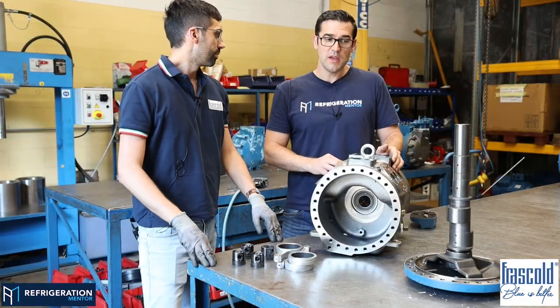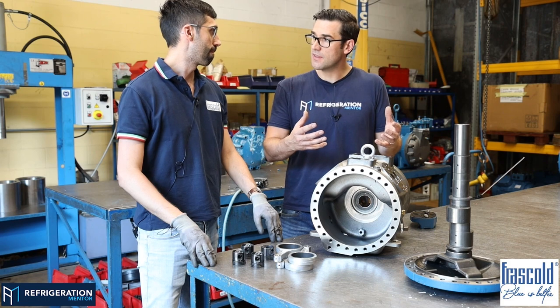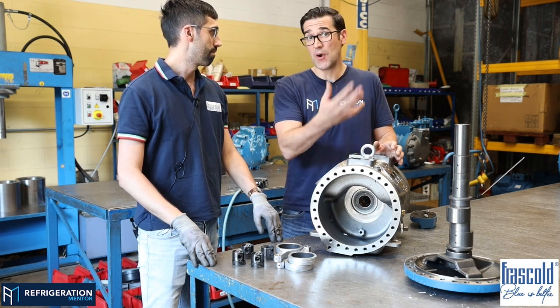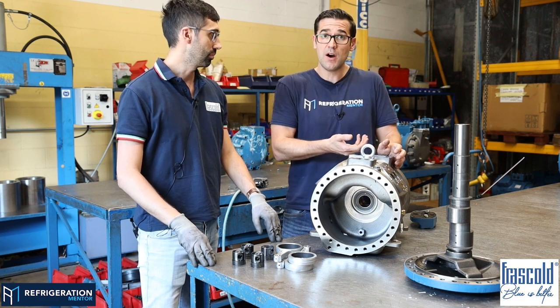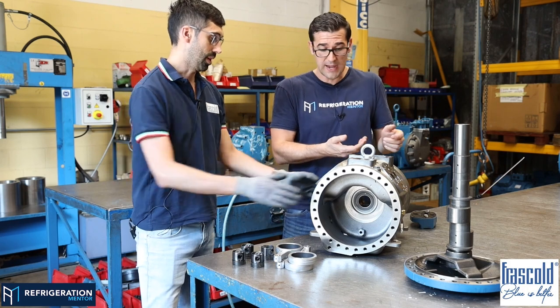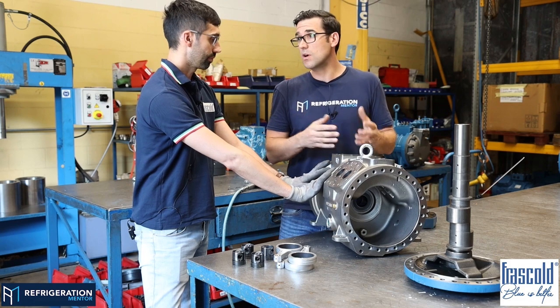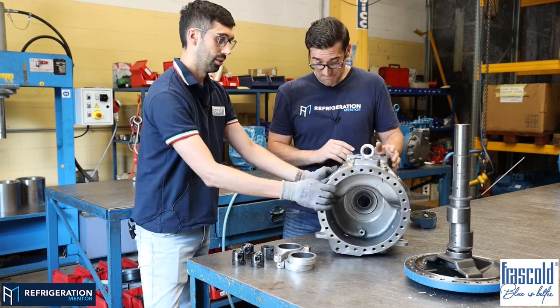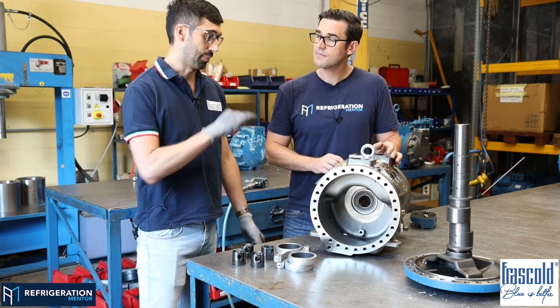Yeah, and so when that seizes up, when a technician comes there and turns the power back on, it could trip the breaker, you hit locked rotor amps. You've got your amp clamp on and you look on the side of the compressor and it's going to say your LRA, or your locked rotor amps, and it's going to give you that number and it trips off. That could be one situation. This surface becomes very hot. Yep. No refrigerant effect, no flow, tripping of the breakers.